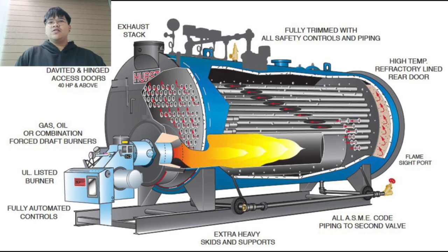So the burner is responsible for preparing the fuel to enter the furnace. The first thing the burner does is atomize the fuel, which means breaking the fuel oil into fine droplets. This is important because fine droplets will burn more efficiently and produce a cleaner flame.